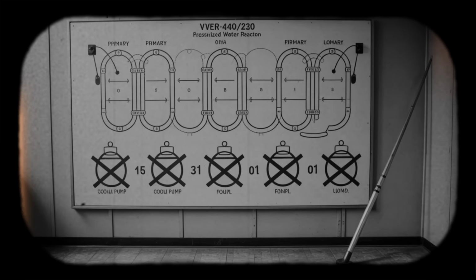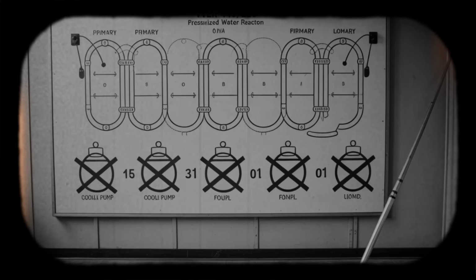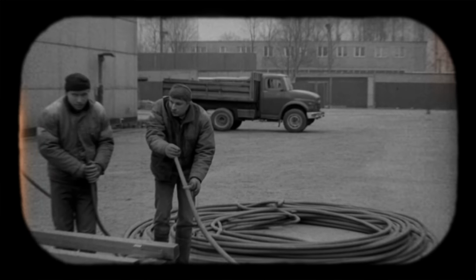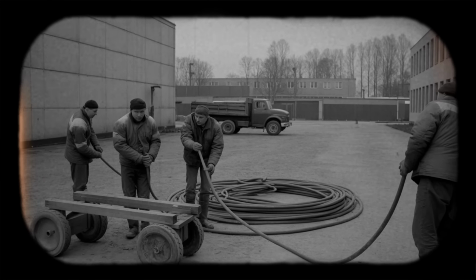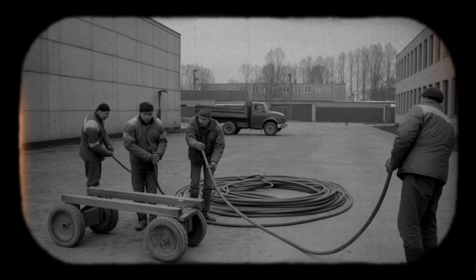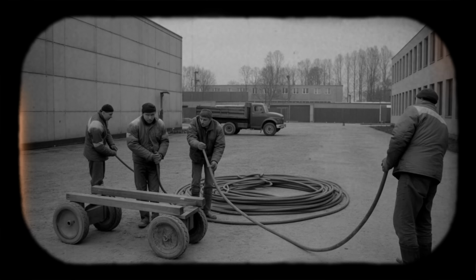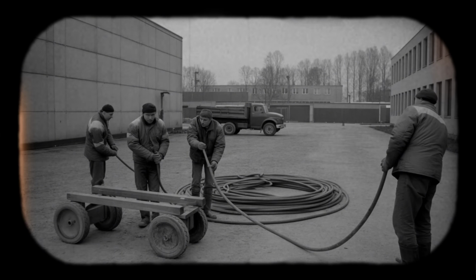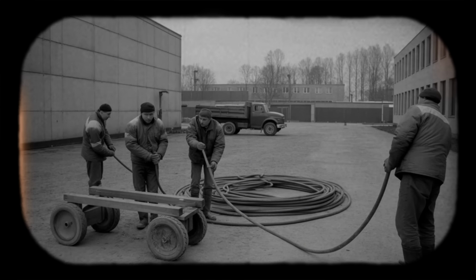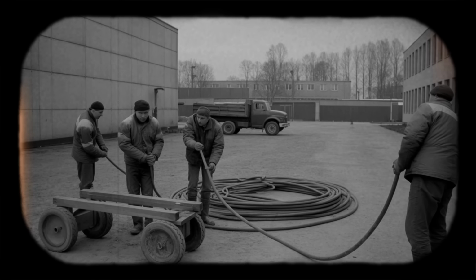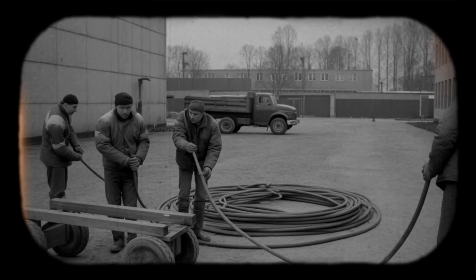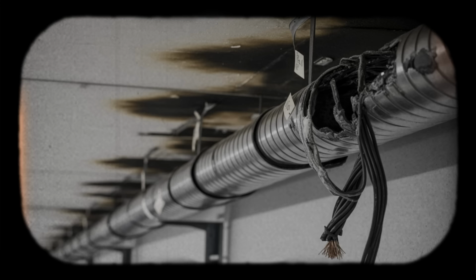Instrumentation channels degraded. Design documents had assumed that structural separation between turbine and reactor buildings, plus some degree of train separation, would prevent this. They had not assumed a shared intermediate building with a main cable route carrying multiple critical systems together. That assumption was now invalidated by fire and smoke. The reactor scrammed. Turbine tripped. Main coolant pumps lost power and coasted down. All within minutes of the cable fire alarm, the control room filled with alarms, not the pattern of a single equipment failure, but the cascade signature of a common cause event affecting multiple systems simultaneously.